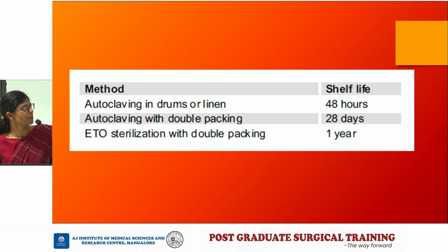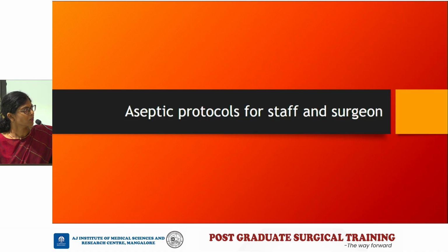So the thing to remember here is that for autoclaving in drums or linen, the shelf life is just 48 hours. Whereas if you autoclave with double packing, like in a B-class autoclave, then you can keep it for around 28 days. And ETO sterilization with a double packing usually can be kept for a year. Now this is what I would like to stress today, aseptic protocols for the staff and surgeon.